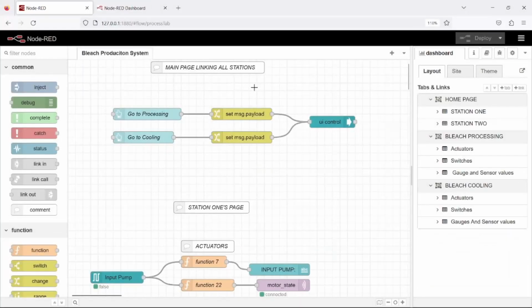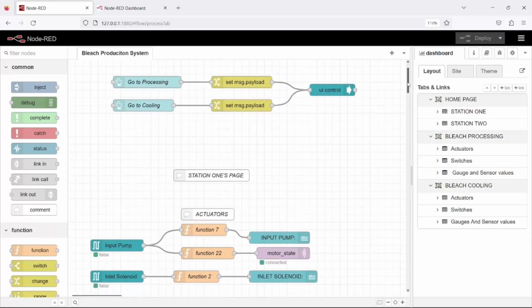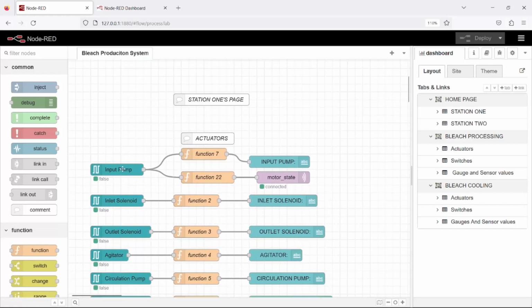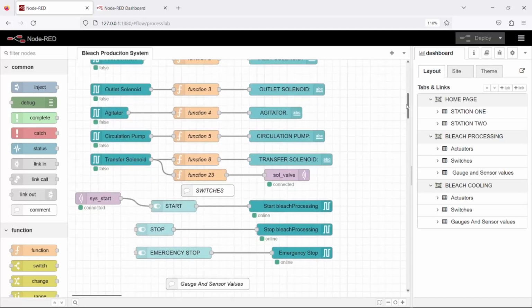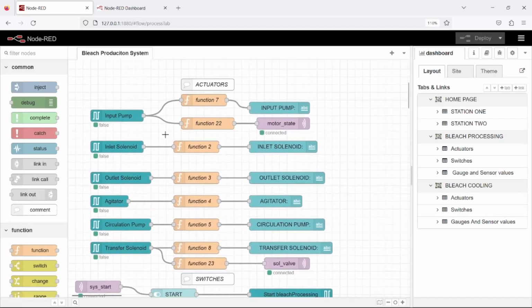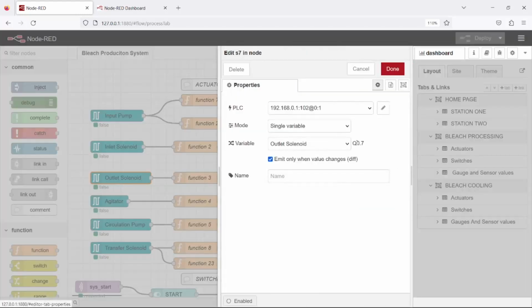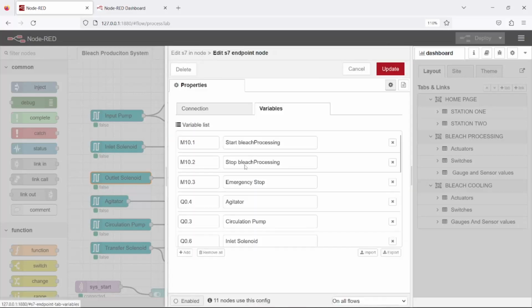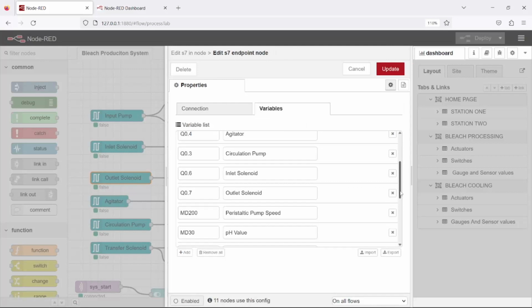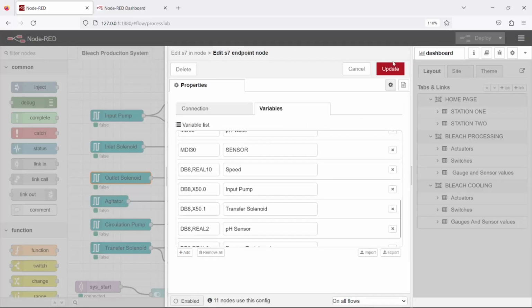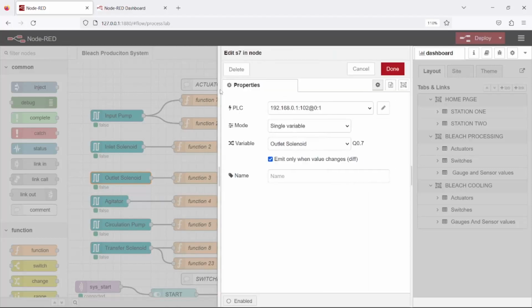Here we have the Node-RED code that we had implemented for the SCADA. These nodes are used for navigation towards the different stations. On the second slide here, we have the nodes for station 1, which is the thermal station, where we've configured different actuators and sensors. This station, this is the input pump, the solenoid for this PLC, and we configured the tags for each actuator to be read from the TIA Portal, also to be able to manipulate using the S7 node.